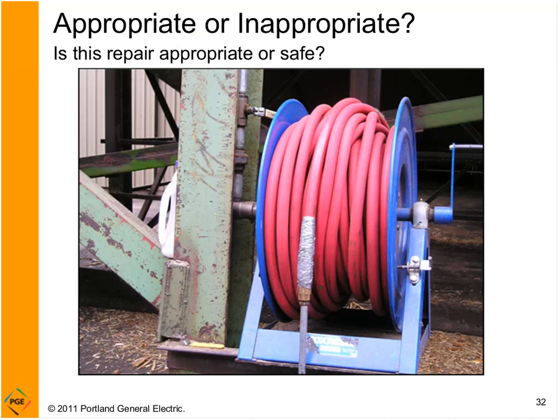Common leak sources: worn hoses (like the one a forklift ran over), worn cylinder packings and glands, valves and regulators, pipe joints and flanges. In a sawmill, constant vibration from logs eventually leads to blown gaskets and leaky joints. In this photo: good old duct tape on a pipe connection — not only a potential leak source since the leak will find its way through, but a safety hazard. If there's an aneurysm inside, it could blow out and become a missile. The positive: the valve is shut off when not in use.